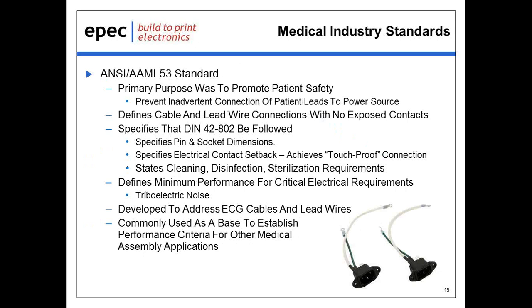So I mentioned that the medical industry is really highly regulated by the use of standards. The manufacture of cable assemblies is not. The relevant standard for medical is an ANSI AAMI 53 standard, and that was developed with the primary purpose of promoting patient safety many, many years ago. The standard originally wanted to prevent the connection of patient leads to a power source and therefore shocking the patient.